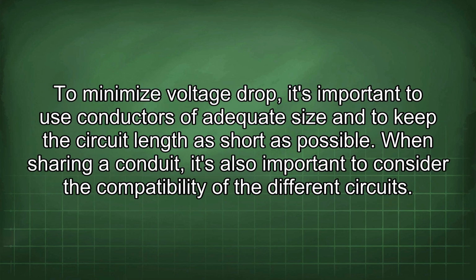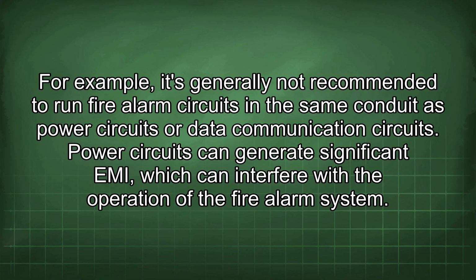To minimize voltage drop, it's important to use conductors of adequate size and to keep the circuit length as short as possible. When sharing a conduit, it's also important to consider the compatibility of the different circuits. For example, it's generally not recommended to run fire alarm circuits in the same conduit as power circuits or data communication circuits.